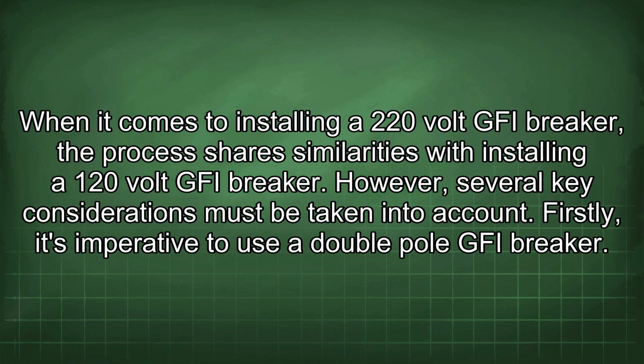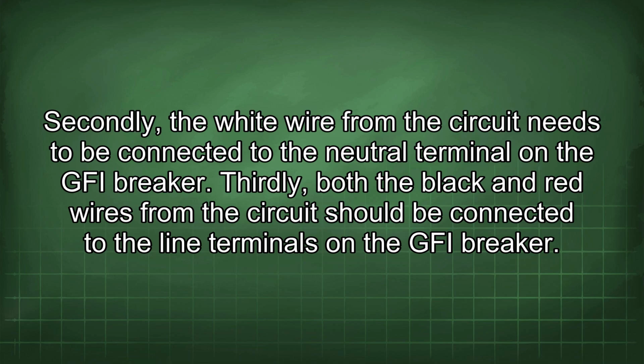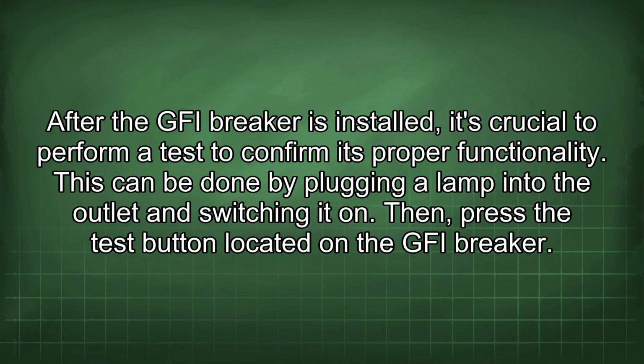When it comes to installing a 220-volt GFI breaker, the process shares similarities with installing a 120-volt GFI breaker. However, several key considerations must be taken into account. Firstly, it's imperative to use a double-pole GFI breaker. Secondly, the white wire from the circuit needs to be connected to the neutral terminal on the GFI breaker. Thirdly, both the black and red wires from the circuit should be connected to the line terminals on the GFI breaker. After the GFI breaker is installed, it's crucial to perform a test to confirm its proper functionality.